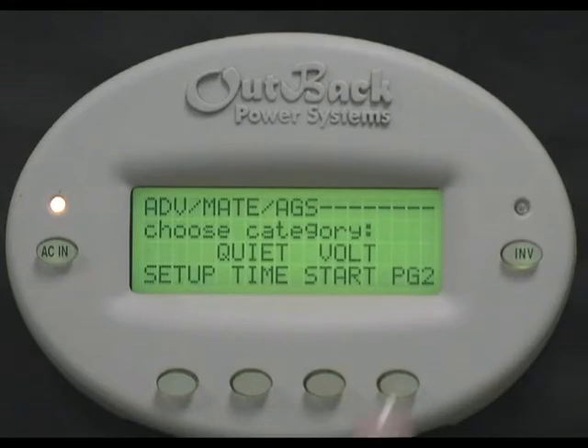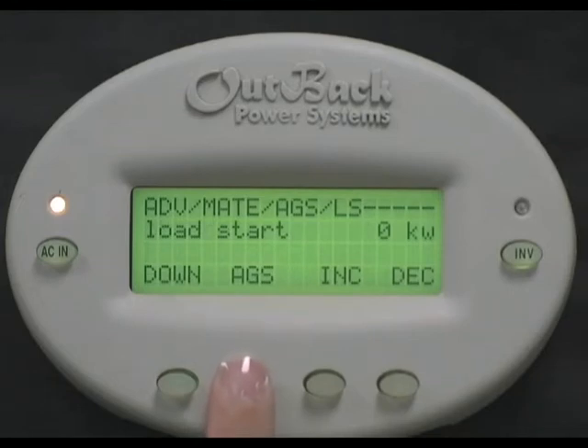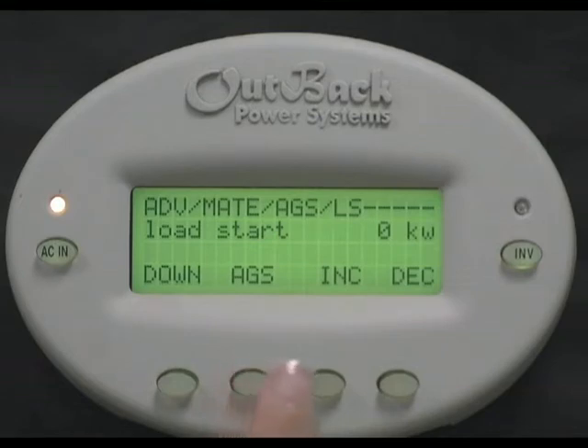Select page two for more settings. Select load start if you want the generator to turn on to help power a large load. Load start is how many kilowatts are being asked for from the inverter before it asks for assistance from the generator. For instance, let's say you have a VFX 3648 and your load size goes above 4kw. The inverter can handle this for about half an hour before it will become overloaded, so you'll definitely want to start the generator to help the inverter out.